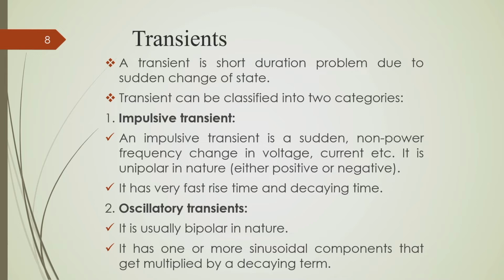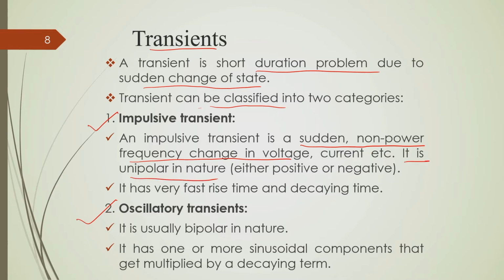Now, let me discuss these power quality problems one by one. We will start with transients. A transient type of power quality problem is a short duration problem due to a sudden change of state. As I said, transients can be categorized as impulsive transients and oscillatory transients. Impulsive means a transient associated with a certain impulse, a sudden non-power frequency change in the supply voltage. Most importantly, it is unipolar in nature. I will show you in my next slide how it looks.